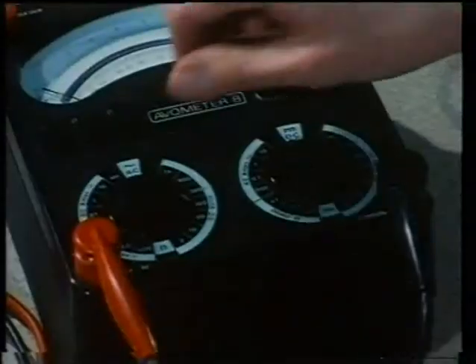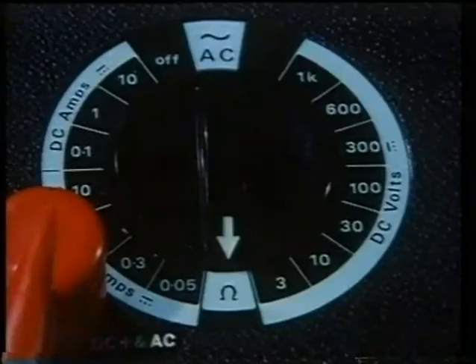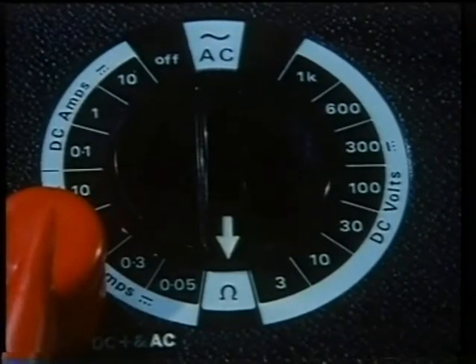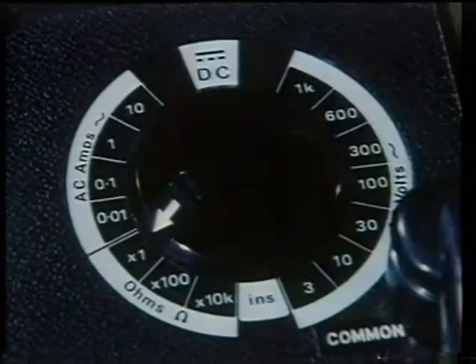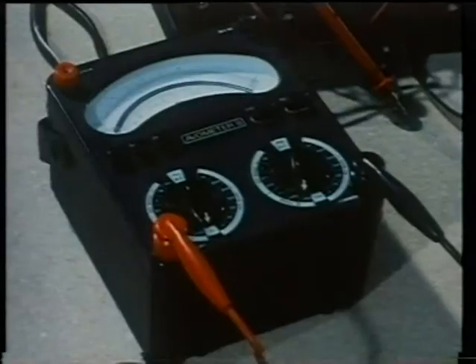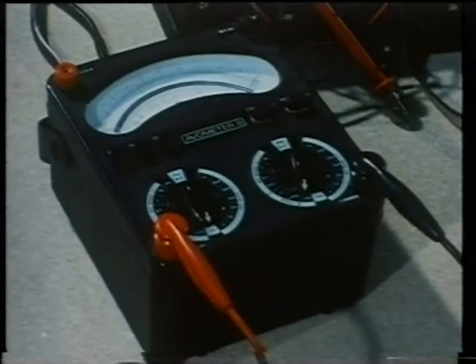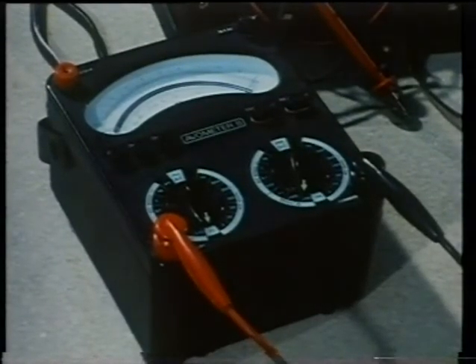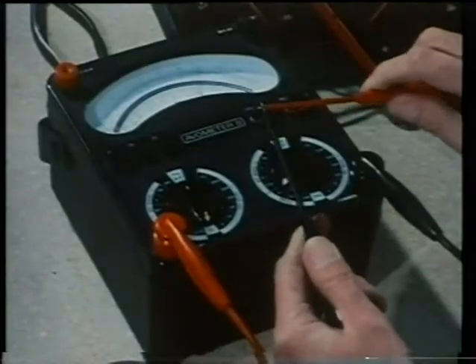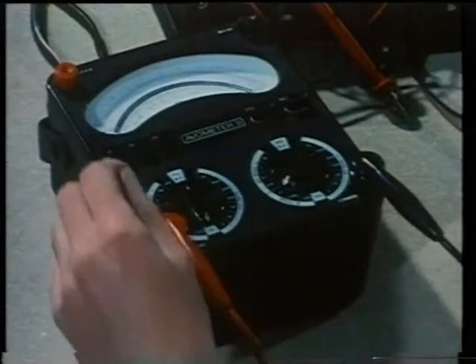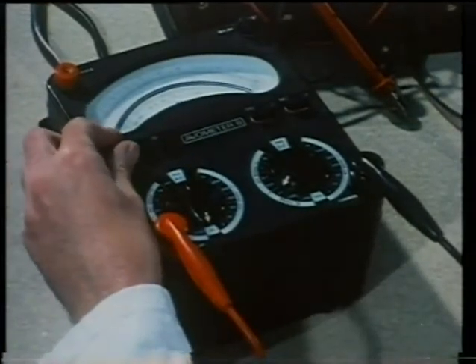The meter can be set to measure the resistance value of a conductor by setting the ohmic system with one dial and with the other dial selecting one of a number of ranges of resistance according to need. Here also the two dials work in combination. For each range of resistance values, the pointer must be set to 0, while the probes of the meter are held together.